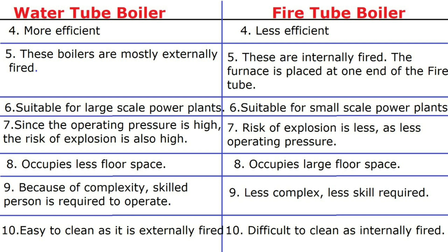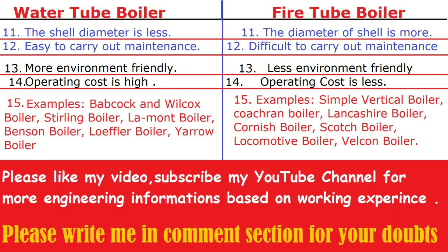Water tube boilers are mostly externally fired, while fire tube boilers are internally fired, with the furnace placed at one end of the fire tube. Water tube boilers are suitable for large-scale power plants while fire tube boilers are for small-scale power plants. Water tube boilers occupy less floor space, while fire tube boilers occupy large floor space. Because of complexity, a skilled person is required to operate water tube boilers, whereas fire tube boilers are less complex so less skill is required. Water tube boilers are easy to clean as they are externally fired, and difficult to clean as they are internally fired.